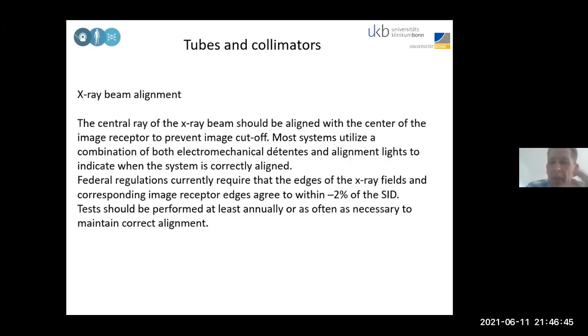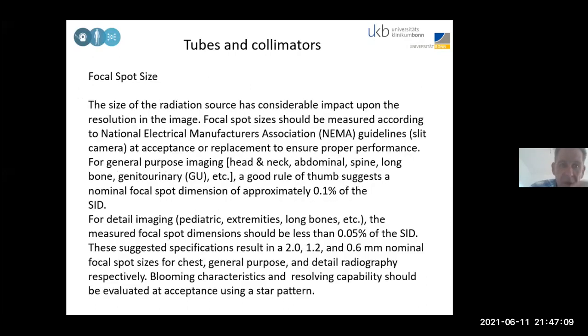Beam alignment. So be sure that your central axis of the central X-ray beam is not angulated or deviated or has torsion. So check the field size and check the center axis, also within 2% of the SID. Focal spot size is maybe something you are not really familiar with, but the focal spot size really has a huge impact on your image quality. And how to check that?